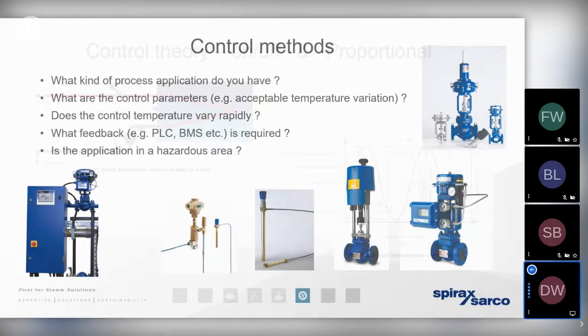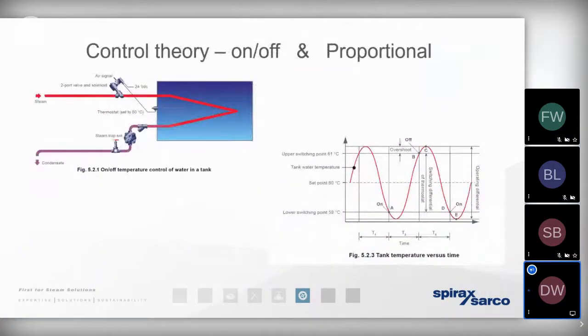So with regards to understanding the control philosophy of the heat exchange in a little bit more detail, well, the most basic control of heat transfer is what we refer to as on-off. That's where the valve is either fully open or fully closed and nowhere in between. So it's a bit like turning your lights on at home. You've got the on switch and the off switch. Very, very coarse control, very crude. It's not suitable for every application, as you can probably understand.